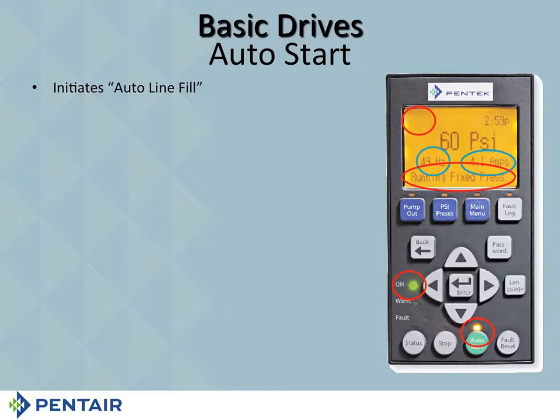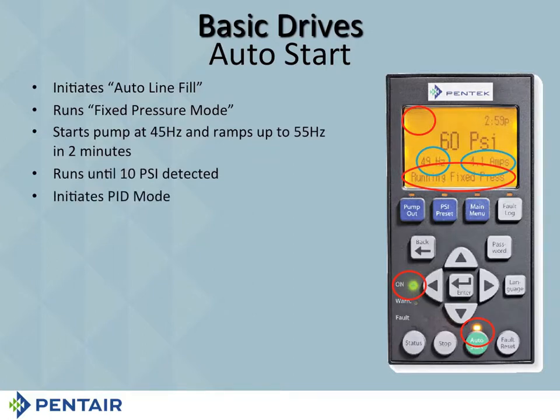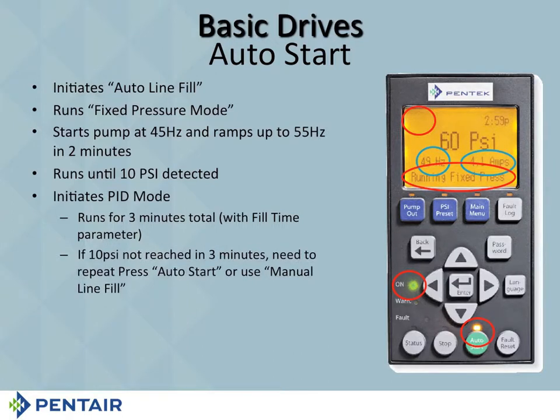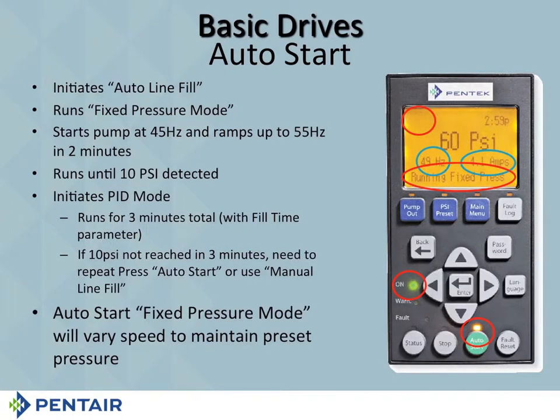It will say 45 hertz, and when your pressure gets to 10 psi, then it will go ahead and kick in and start running at max, okay? Otherwise, it's going to run at 45 hertz, slowly build up to 55, trying to get to that 10 psi. Once 10 psi is detected, yes, now it goes into PID mode, and that does not mean Pentair IntelliDrive. It runs for a total of 3 minutes. If it doesn't hit that 10 psi in 3 minutes, it will indeed turn off. All you do at this point, turn it back on. That's all you have to do.